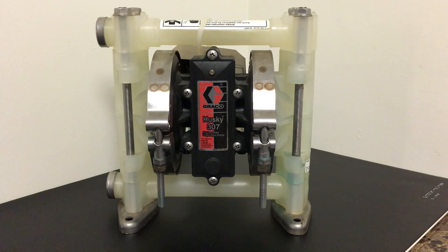If there's no issue there, you want to move on to the air valve which is directly in the center. When I ran this pump, I saw that it would start working for about three to five seconds and cut off. Turn it off, turn it back on, same thing. So I knew that the problem was with the air pressure. I saw my air pressure regulator was working perfectly, so right now I'm very confident that if I go online and order the air valve replacement kit, that'll fix my issue.